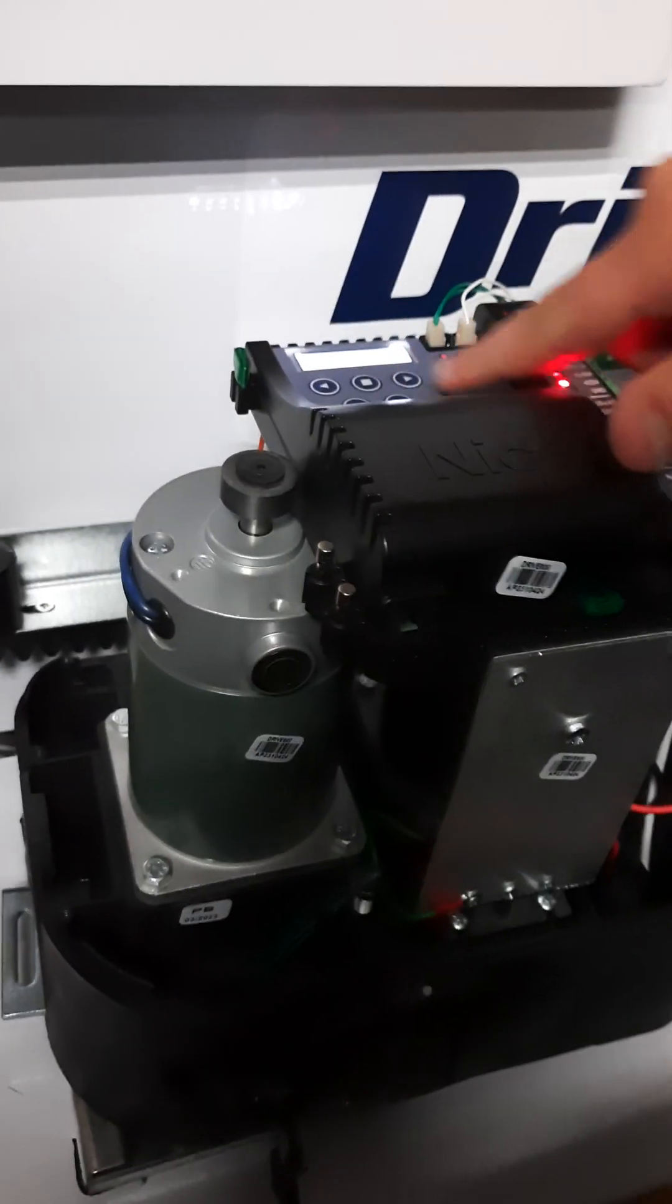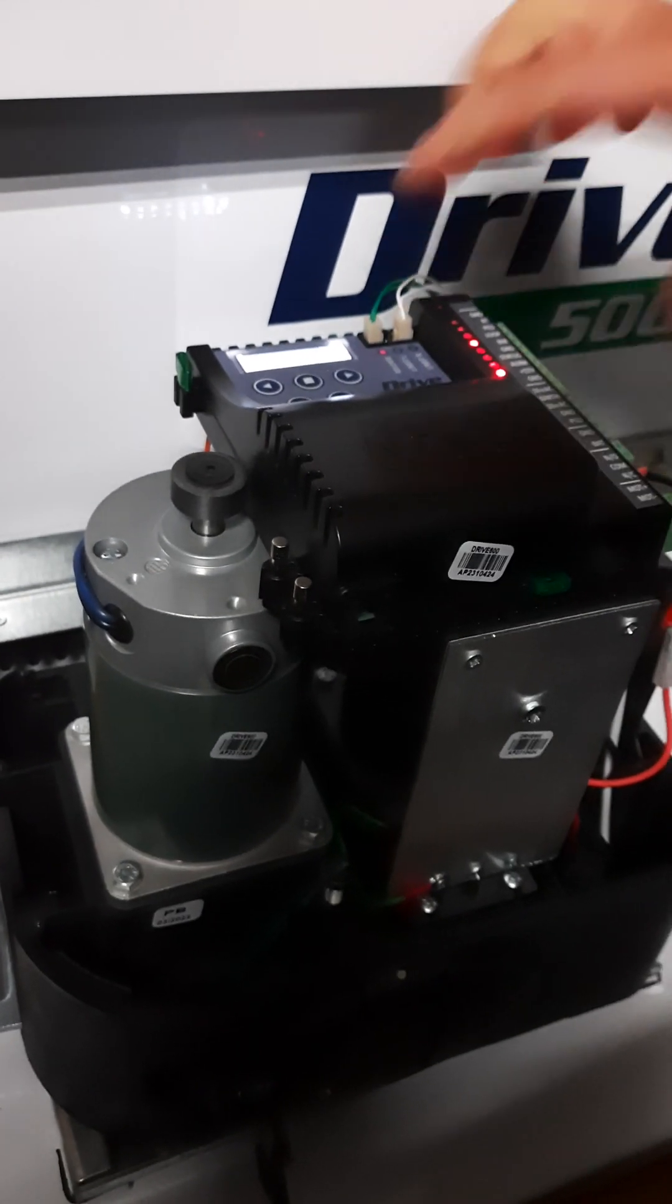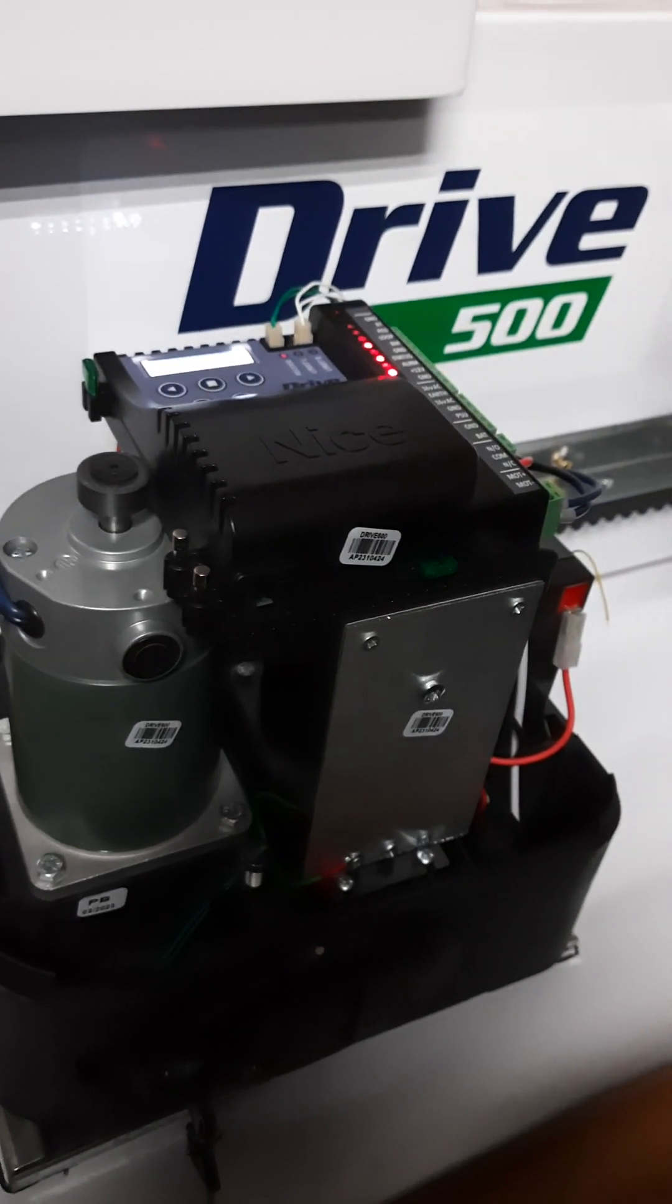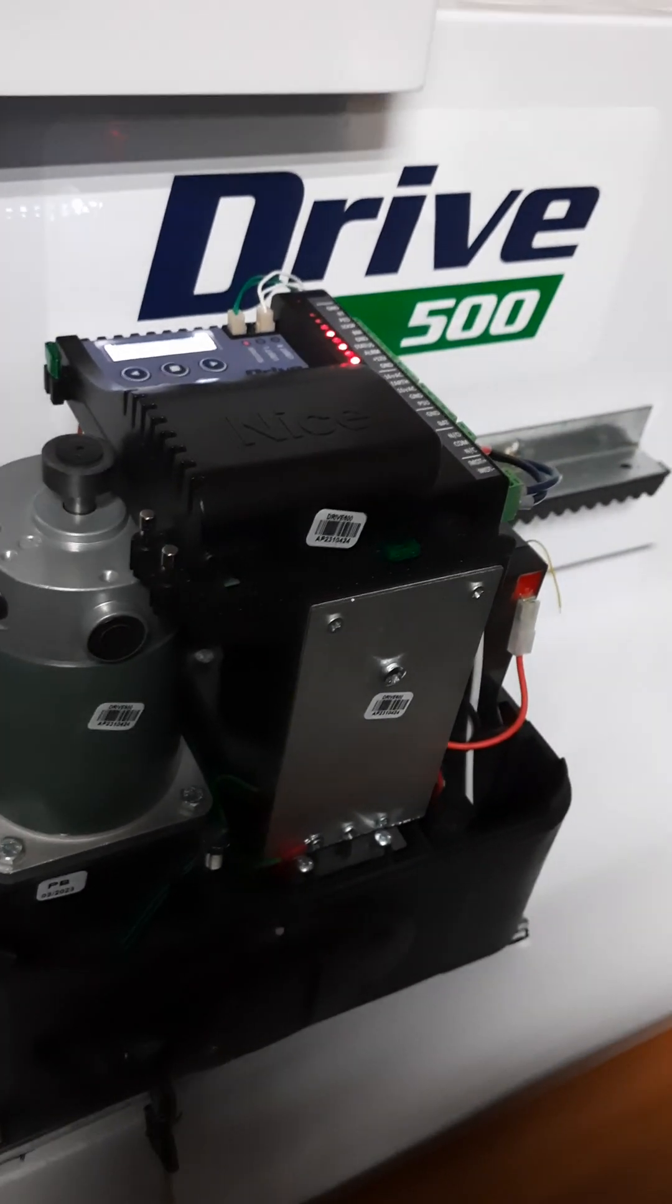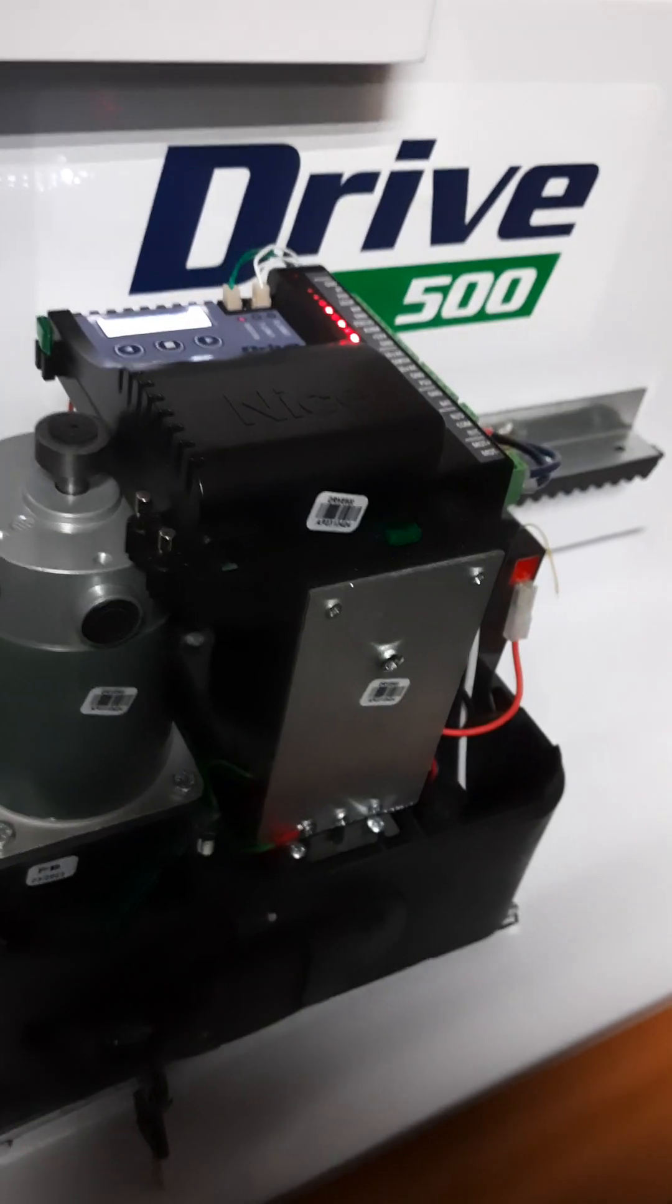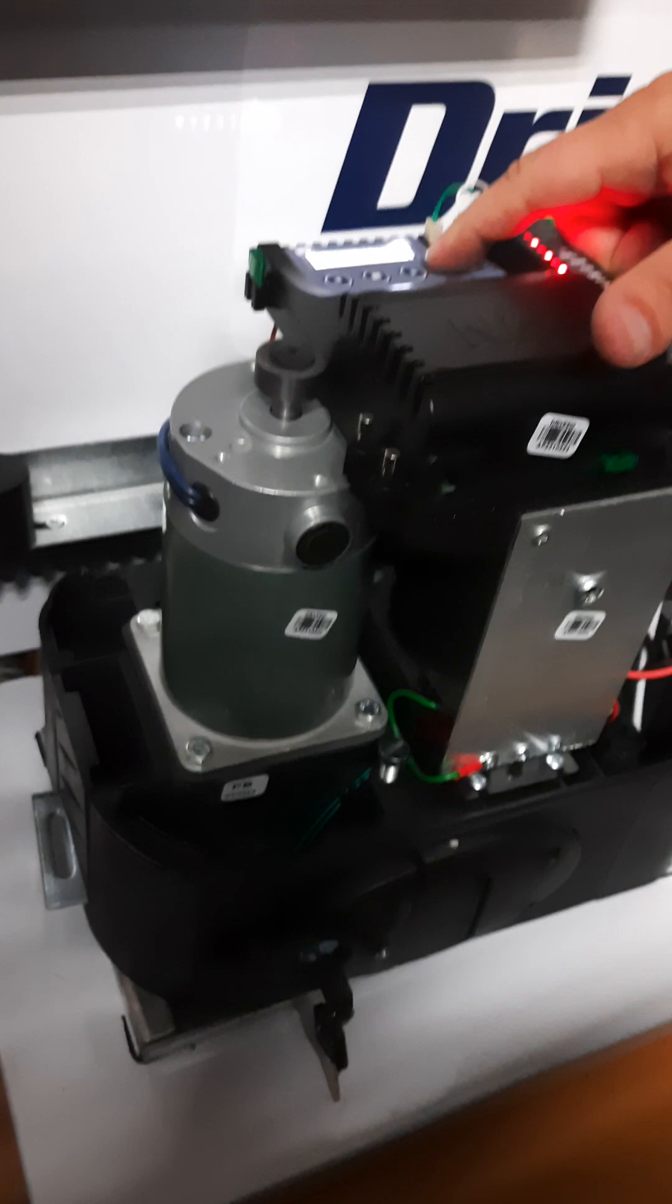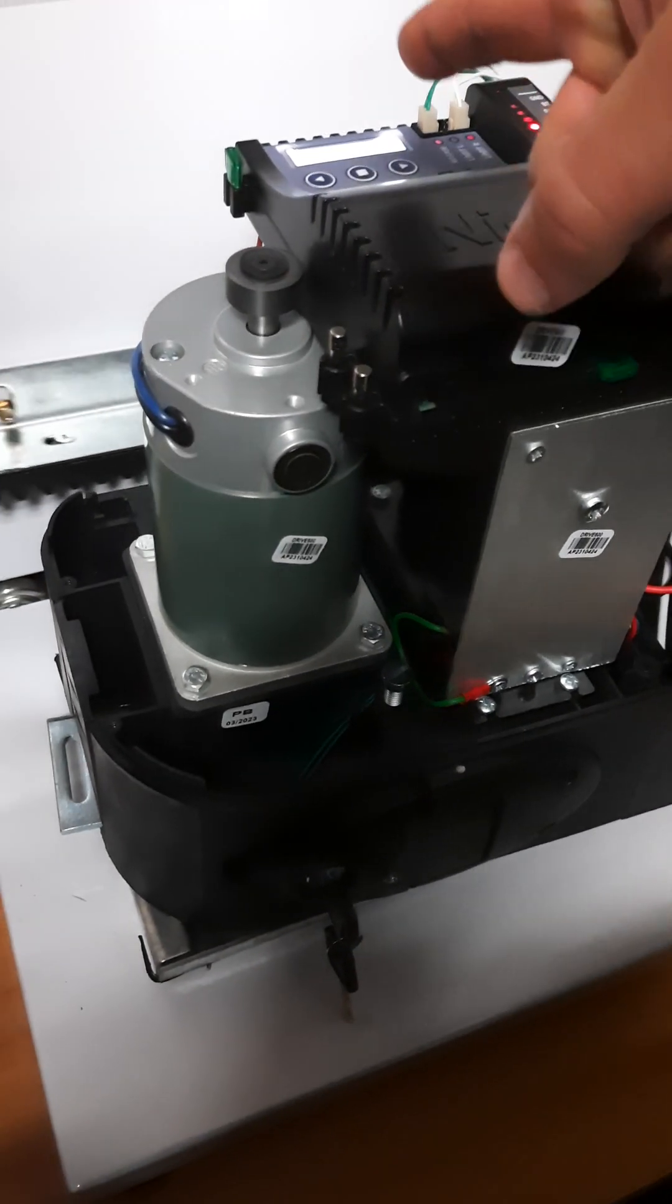Press once to the right. We want to set the limits. So yes, enter. Now the machine is asking me which direction does the gate have to close first. Always close first. If this machine was on the right hand side, it will be closing that way. Now we can press the arrow for the direction and it will run until it sees the magnet.